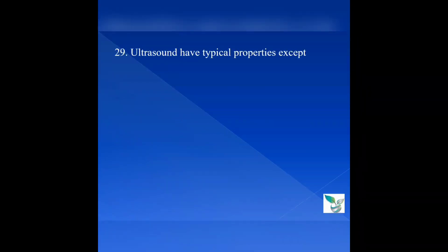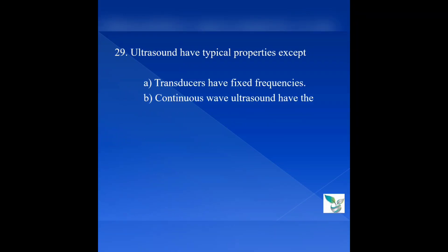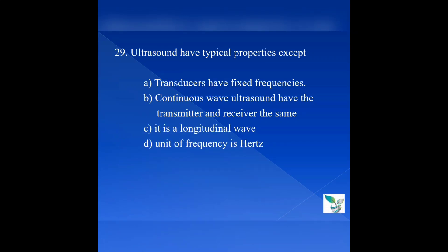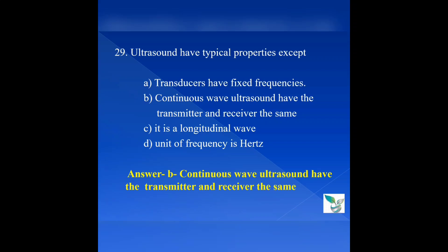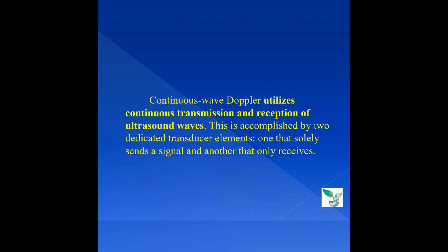Question number 29: Ultrasound has typical properties except — option A, transducers have fixed frequencies; option B, continuous wave ultrasound has the transmitter and receiver the same; option C, it is a longitudinal wave; option D, the unit of frequency is hertz. The answer is option B — continuous wave ultrasound has the transmitter and receiver the same. Continuous wave Doppler utilizes continuous transmission and reception of ultrasound waves, accomplished by two dedicated transducer elements — one that solely sends a signal and another that only receives.